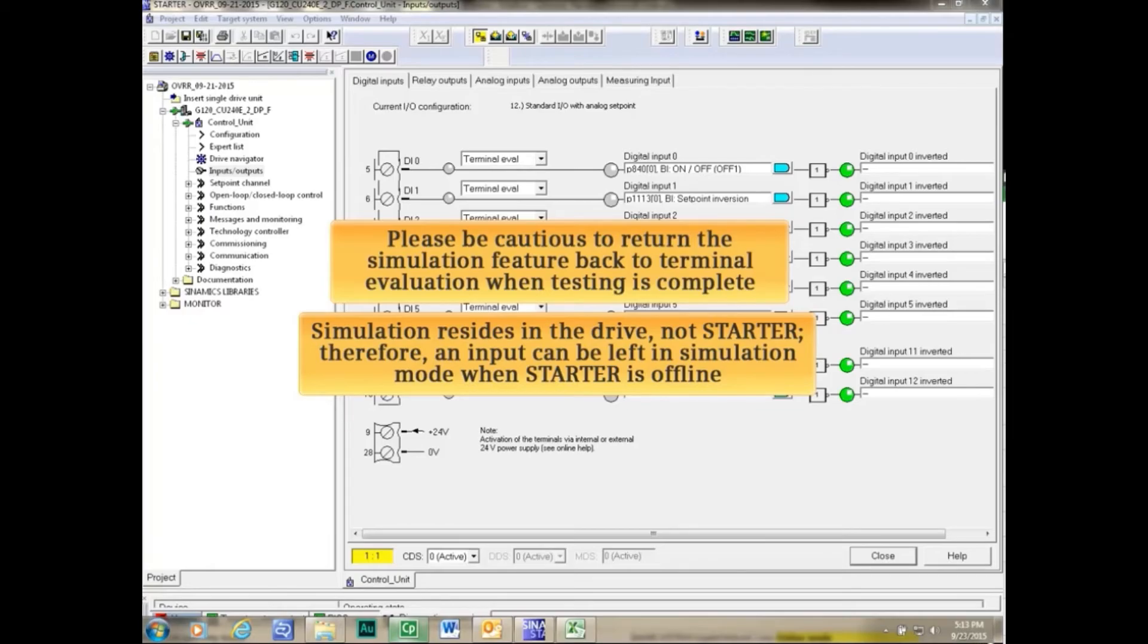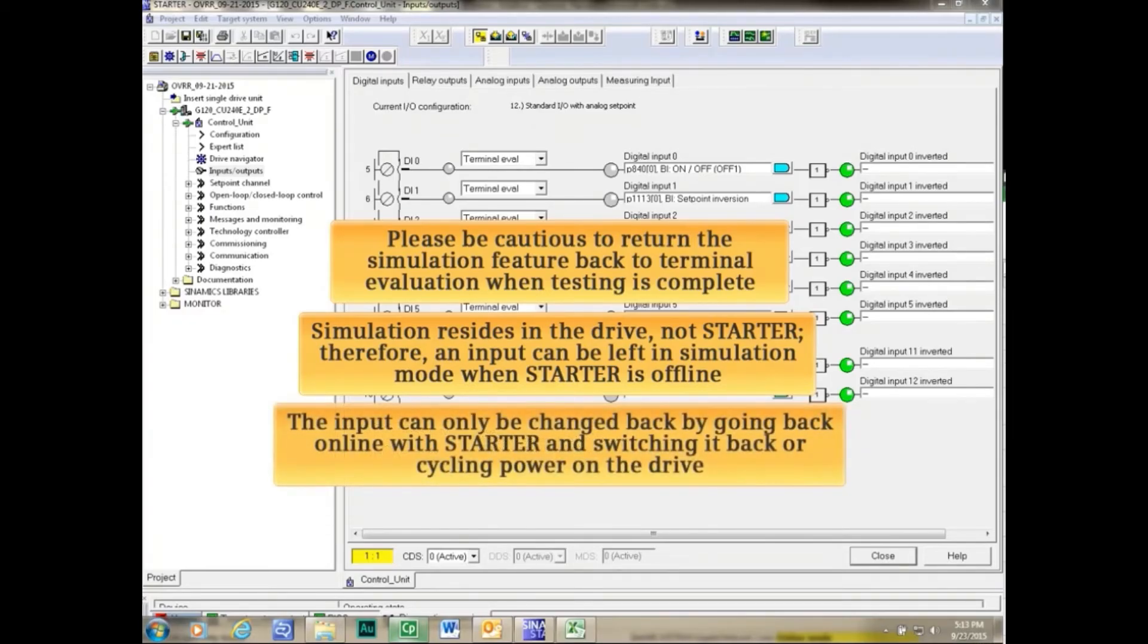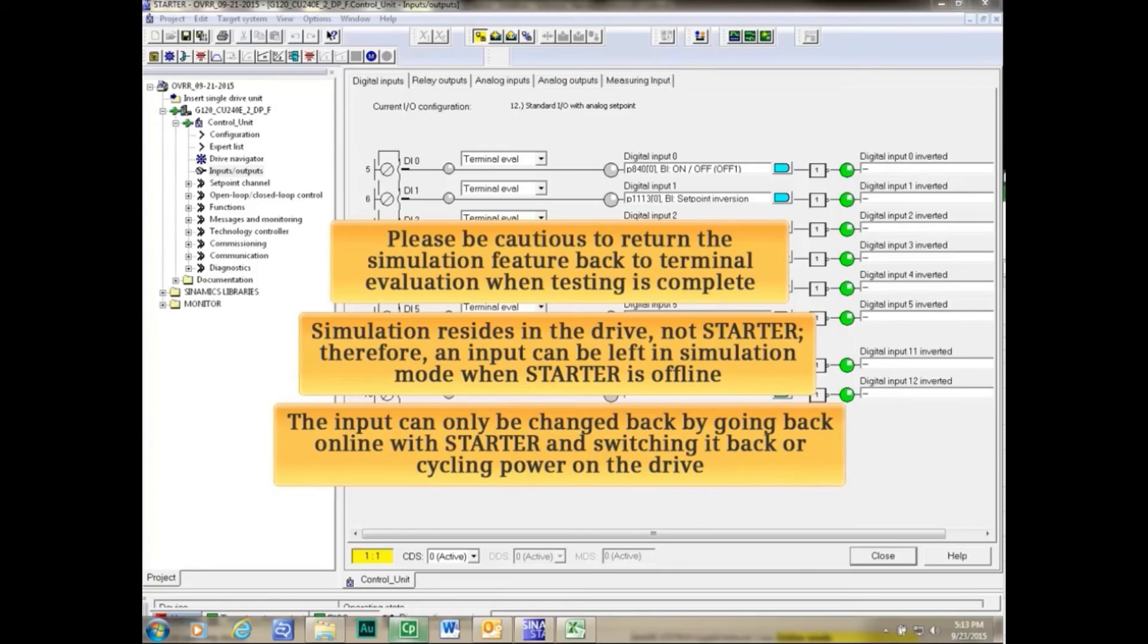Therefore, an input can be left in Simulation mode when Starter is offline. The input can only be changed back by going back online with Starter and switching it back or cycling power on the drive.